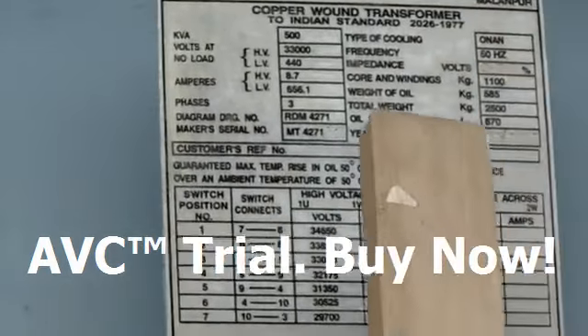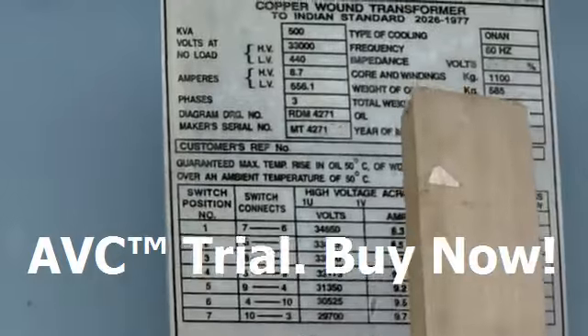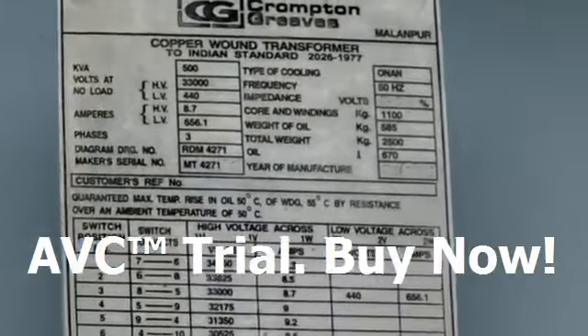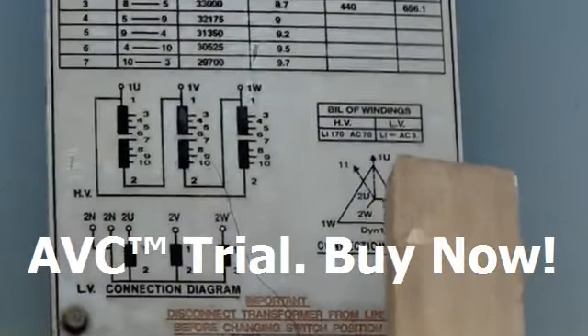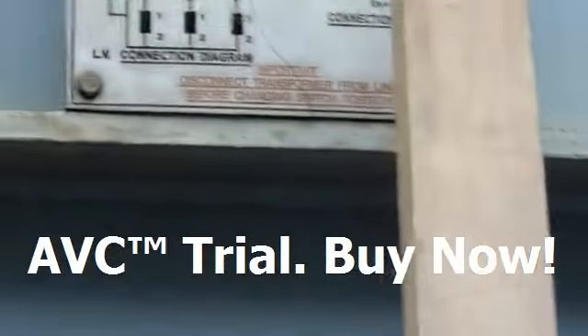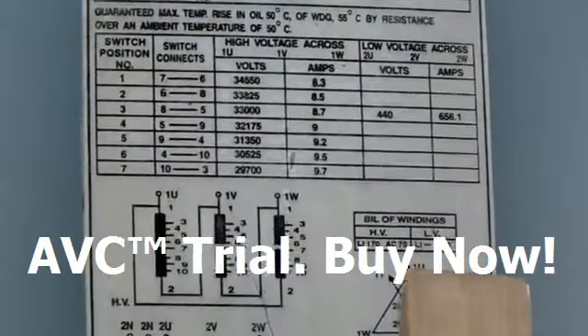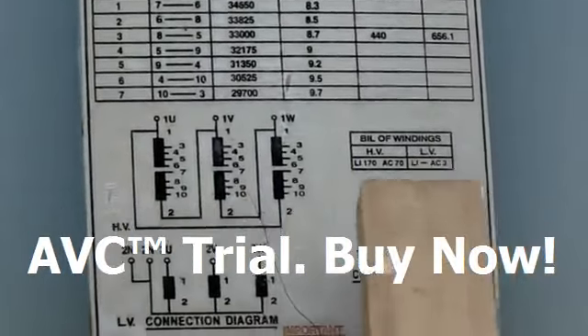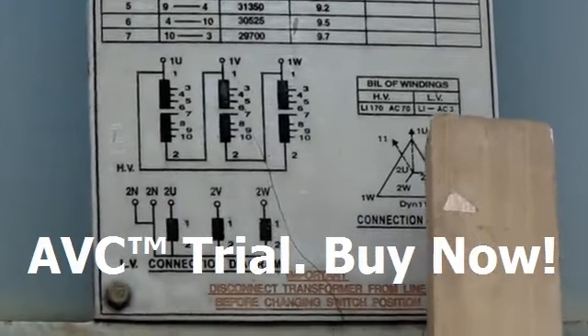of 50 Hz. The other important thing is the vector connection. You can see the vector connection is given here. It is DY11. Normally in all distribution transformers, D stands for the HT side, the primary side, being connected in delta, and Y for the secondary being connected in star, with the secondary side leading the primary side by an angle of 30 degrees. That is known as DY11.